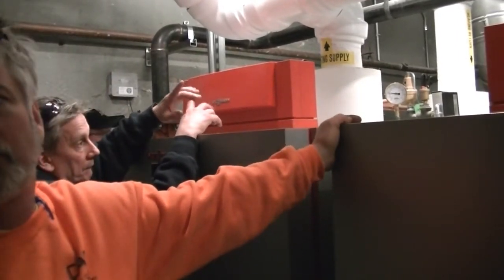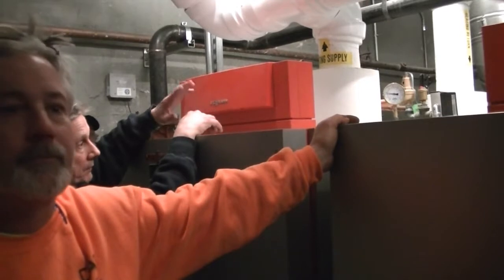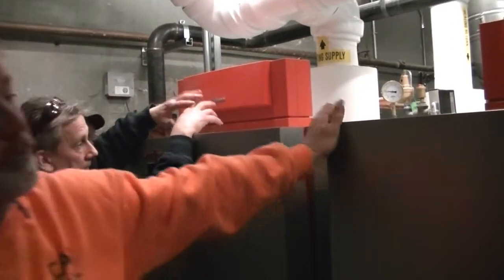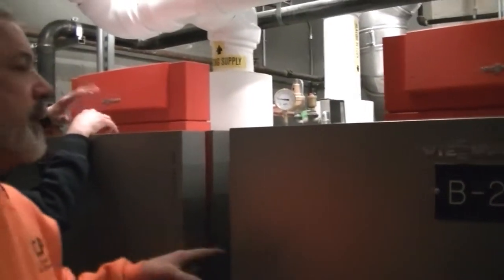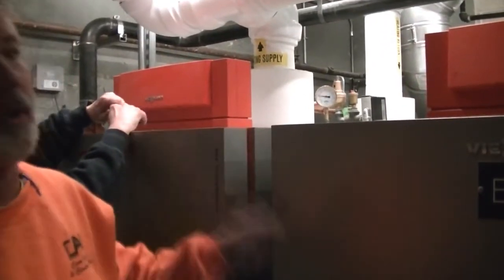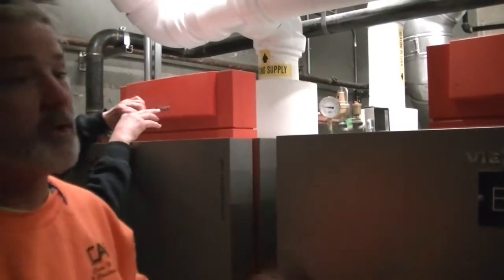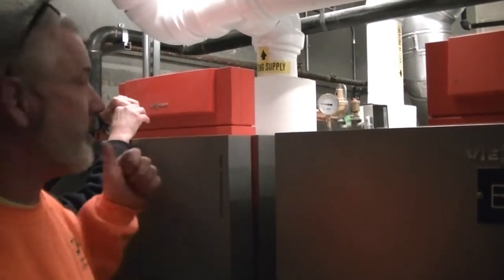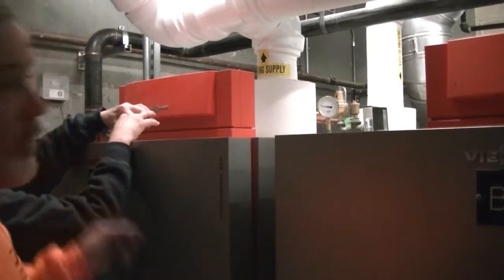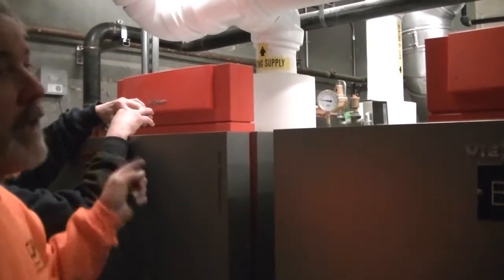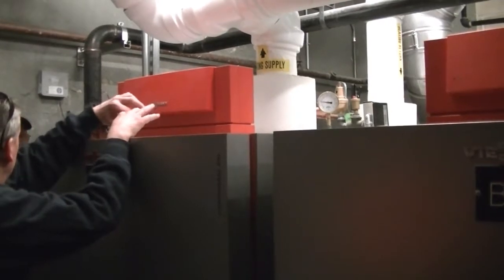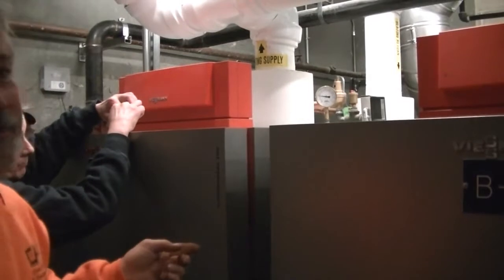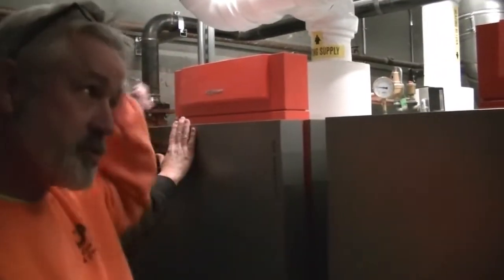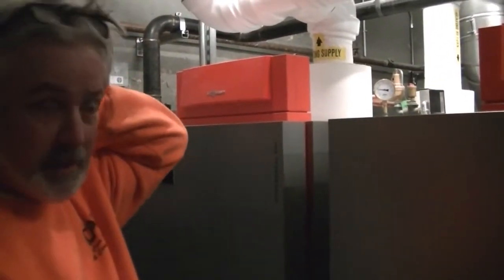Did Kevin show you the low gas pressure switch? He did? Okay. So you know about all the controls in here. Again, one of the most important things is if you walk up to the boiler and you're working on the boiler, take pictures of what you find. If you want to make an adjustment to the boiler, like the heating curve or something, take a picture of that heating curve before you adjust it. Because in 2 days, you're never going to remember what it was before you touched it. You'll know what it is afterwards, but you won't know where you started from, okay?